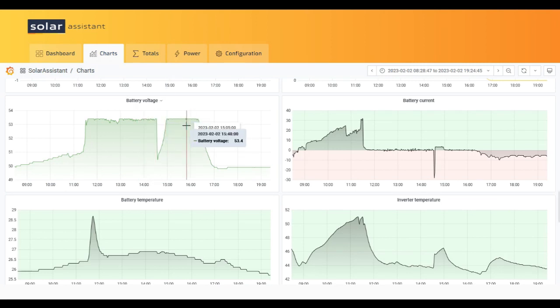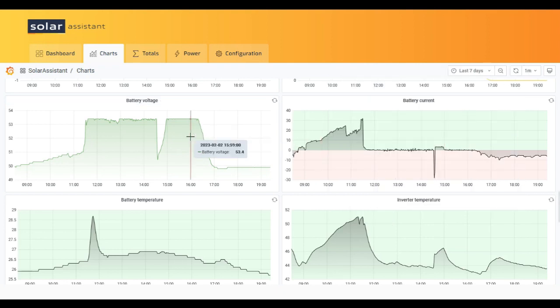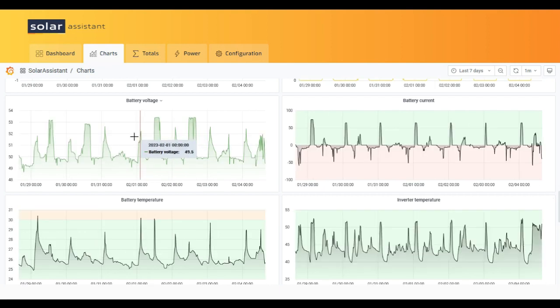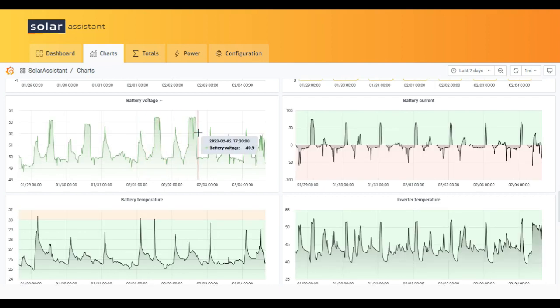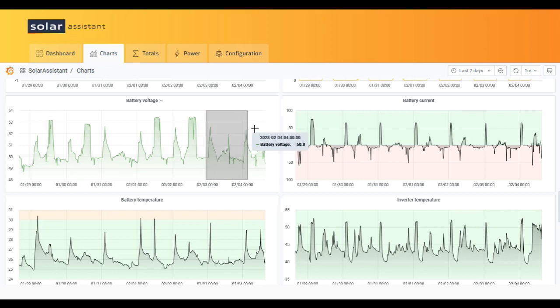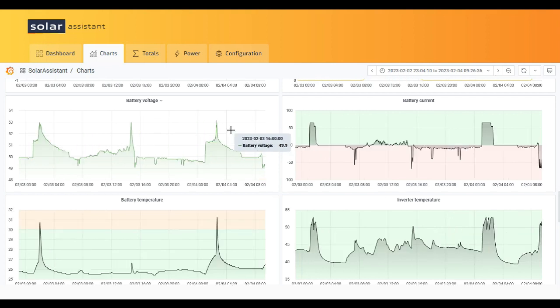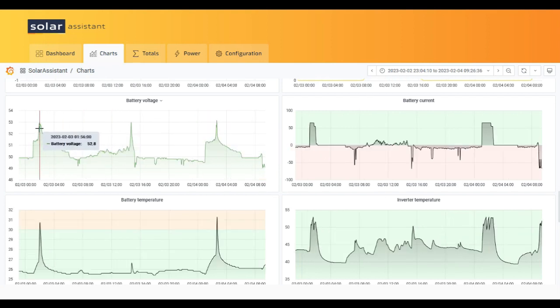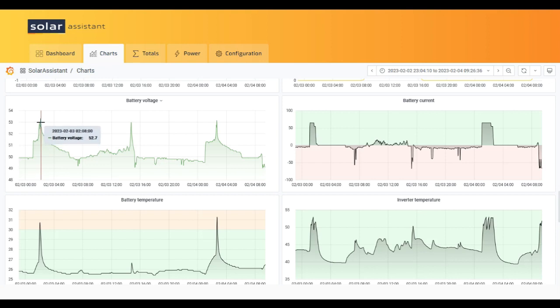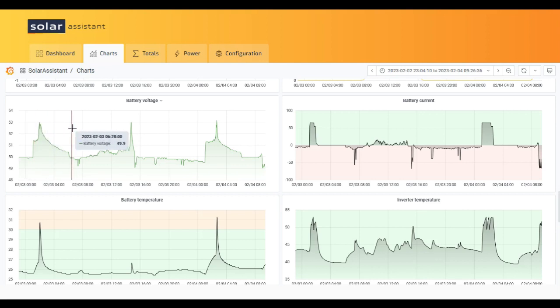This happened because the inverter was not approved for grid export until a few days ago. Now we have enabled the export to grid and you can see, let's try to zoom here, you can see that the voltage goes to 52.8, 53 point something and then drops until around 51 or something like that.